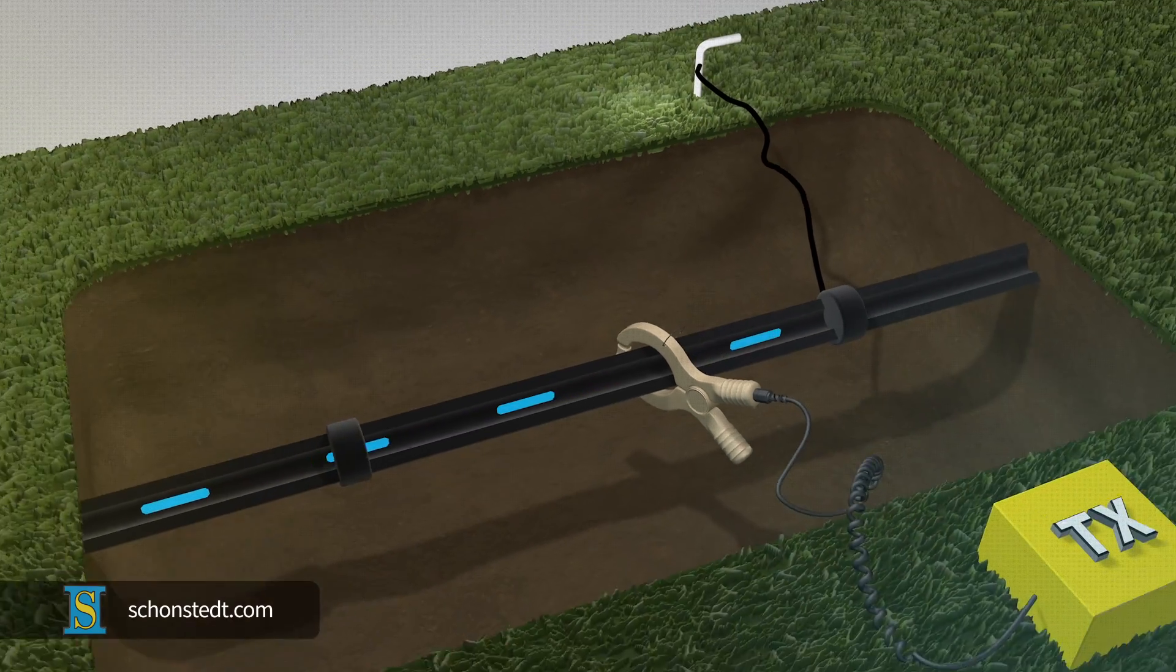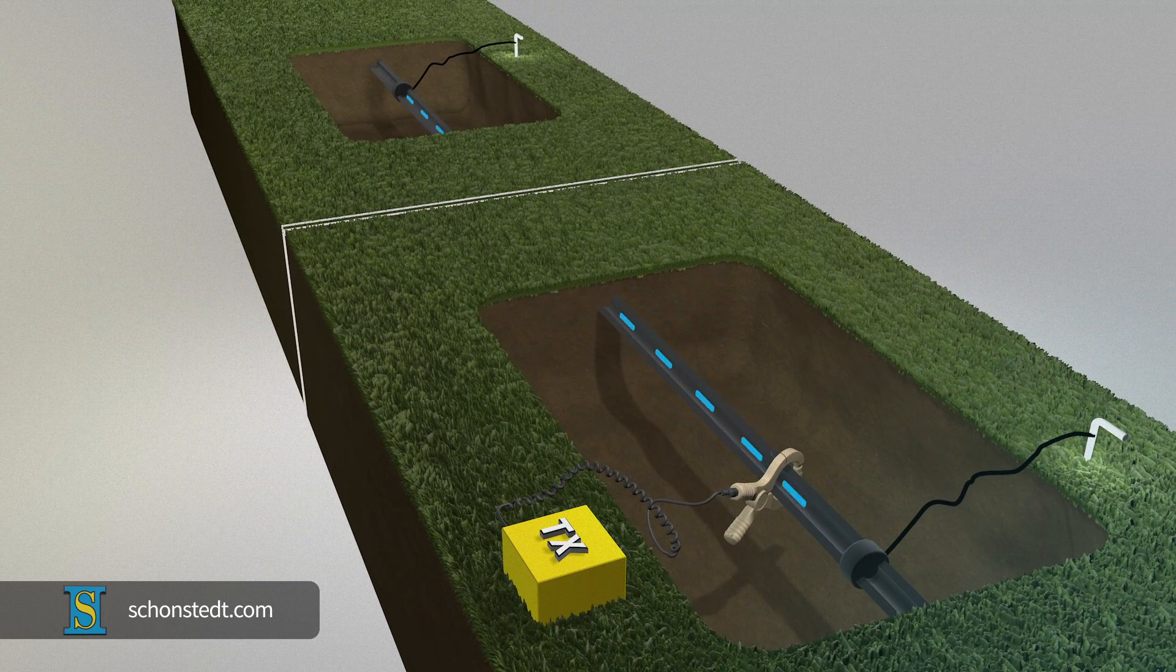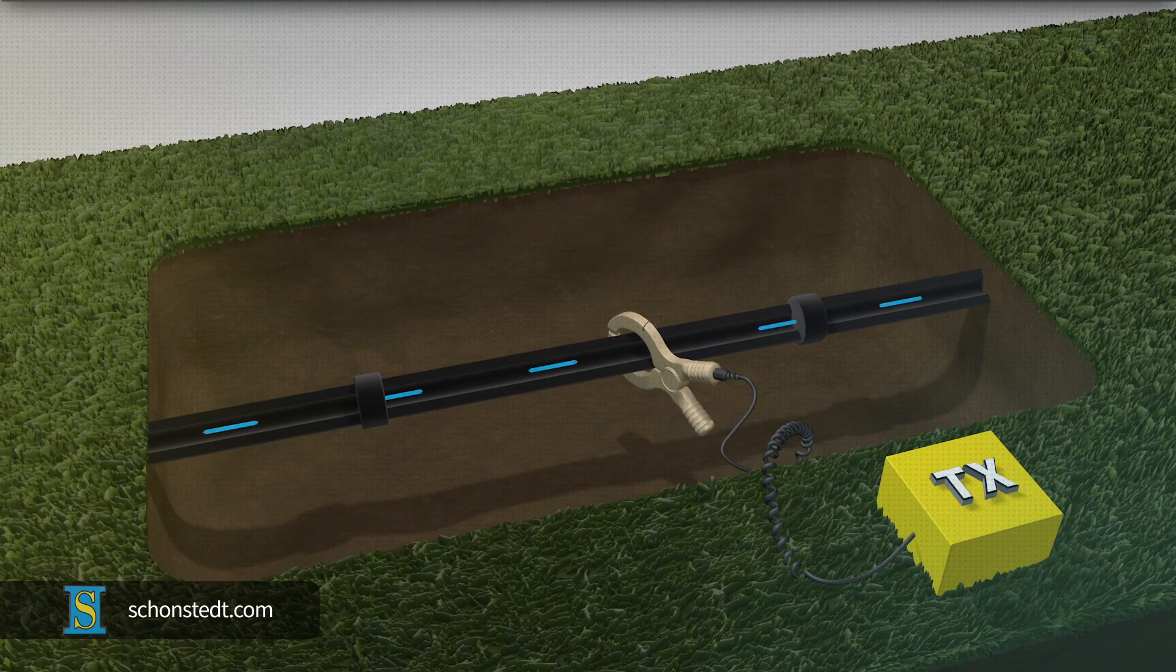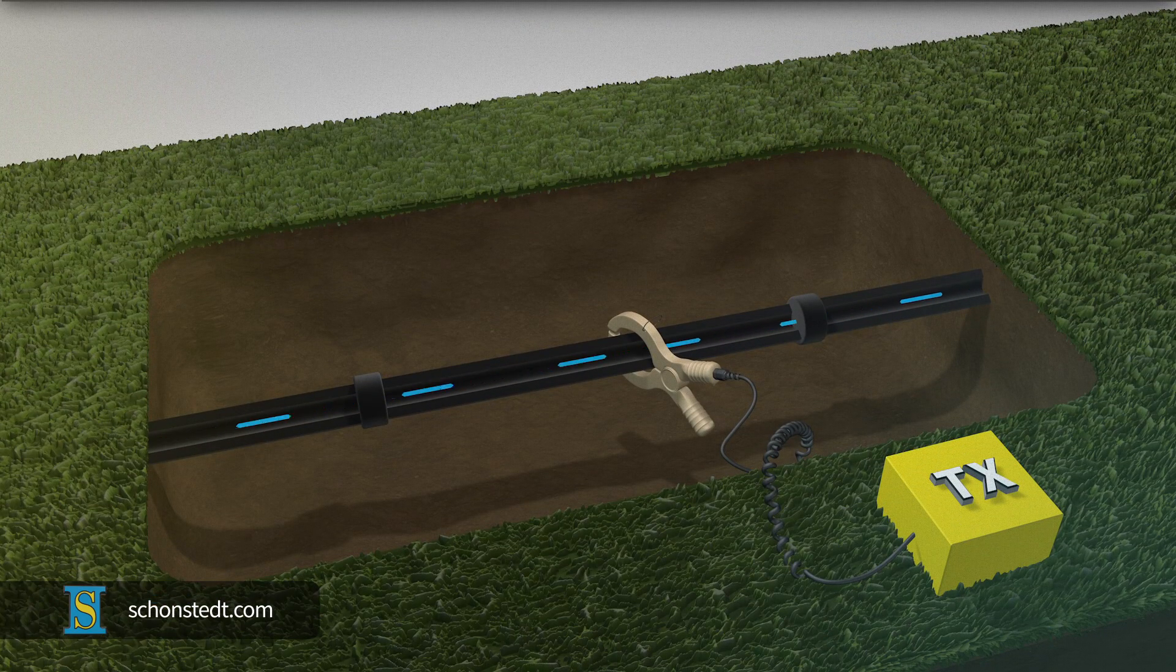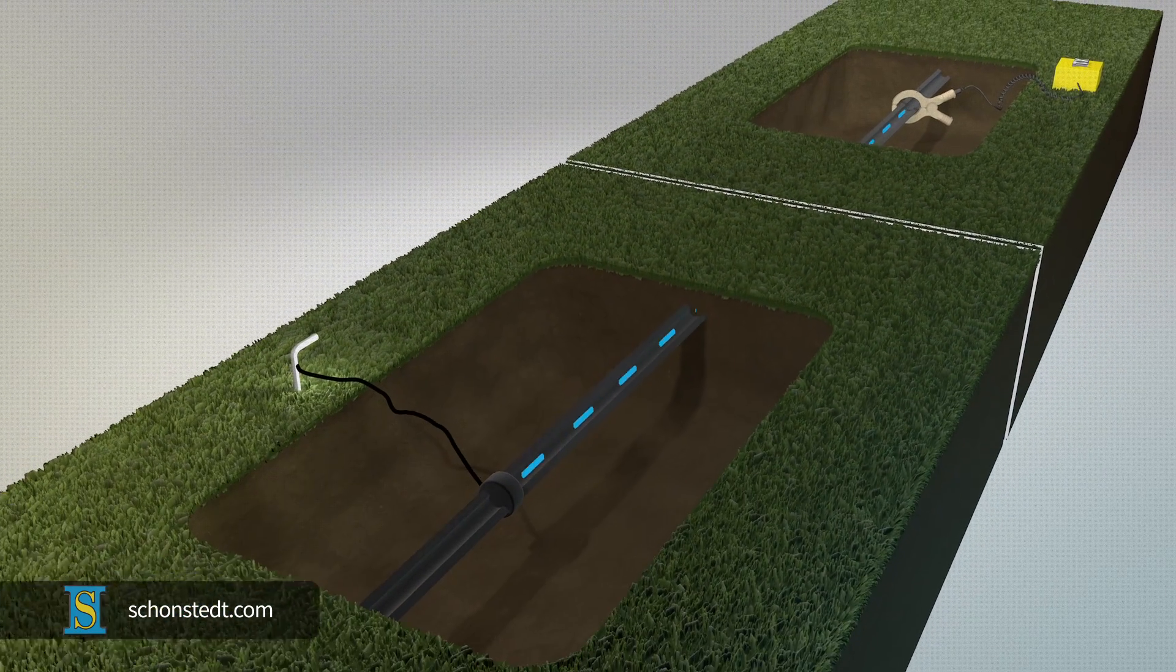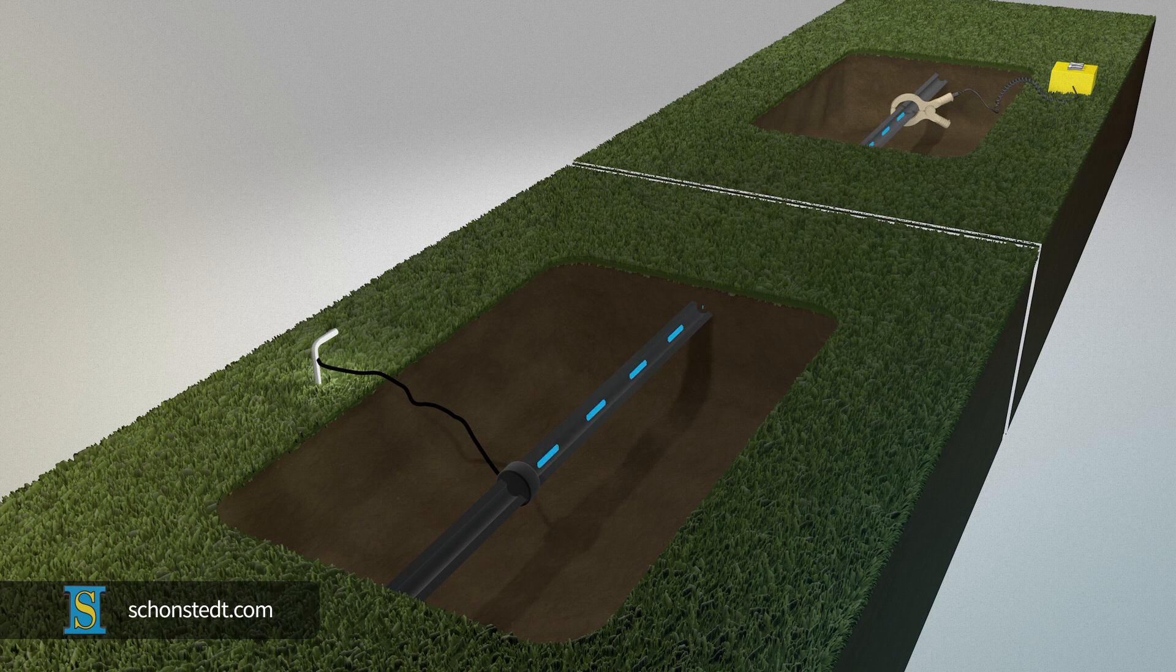At least one end, but preferably both ends—the near and far of the pipe or cable—must be well grounded. Without a ground, the current will be extremely low, which will make locating nearly impossible. If only one end can be grounded, it should be the far end. Otherwise, most of the current will quickly flow from the clamp to the near-grounded end.